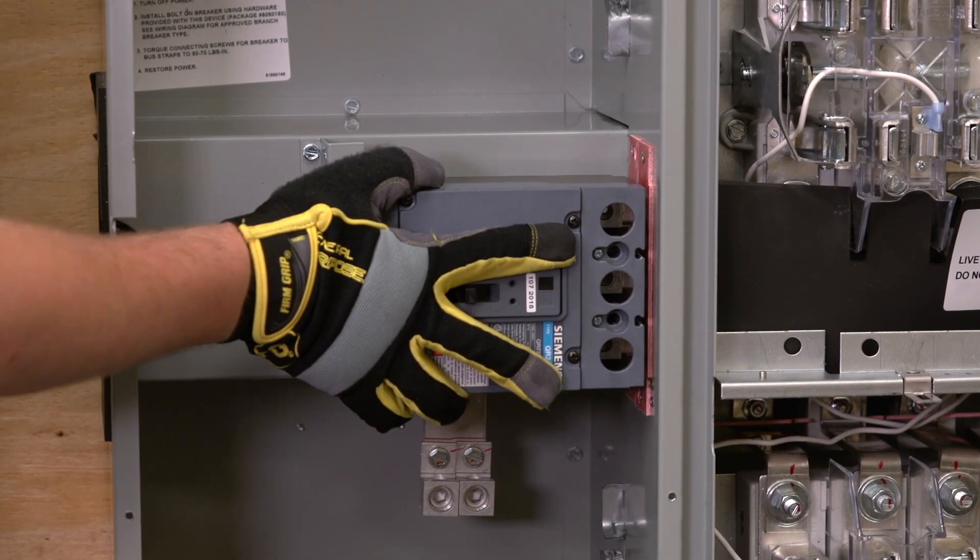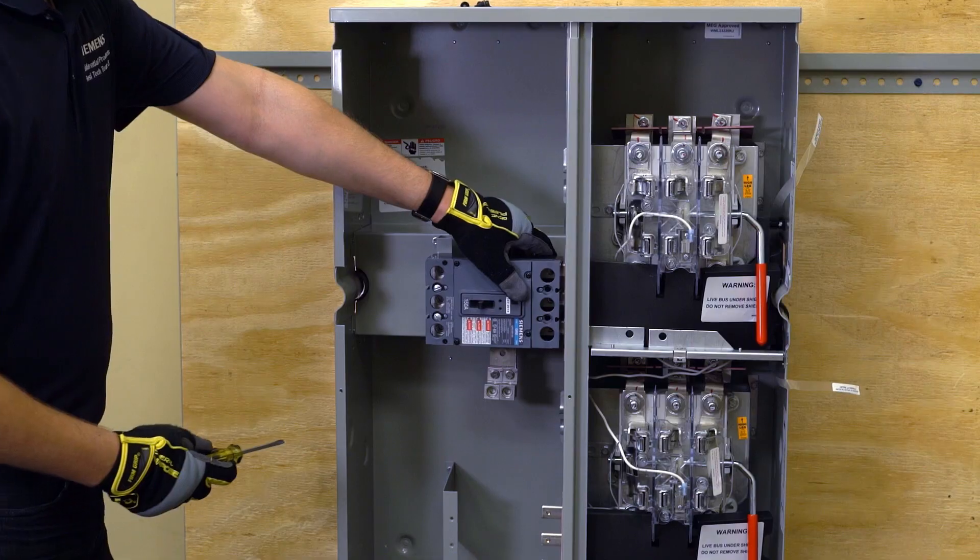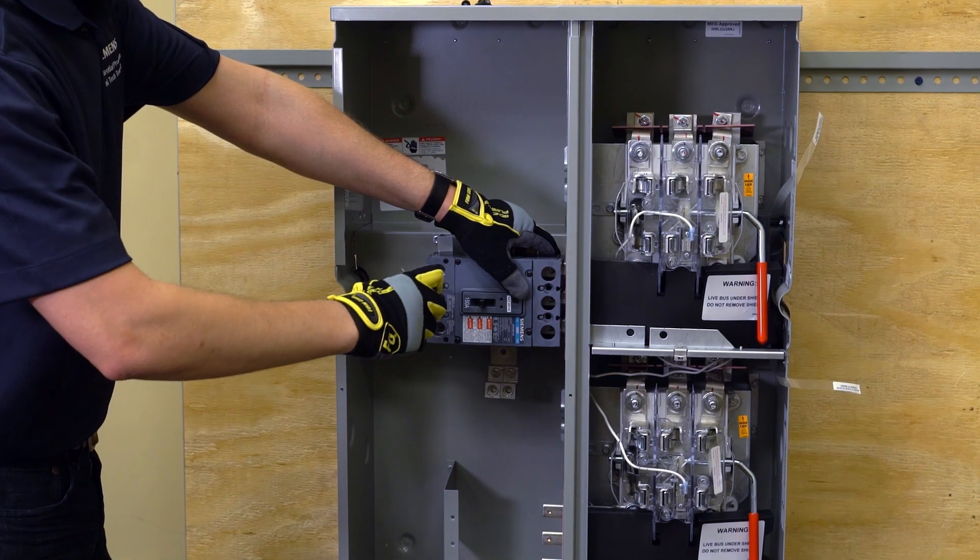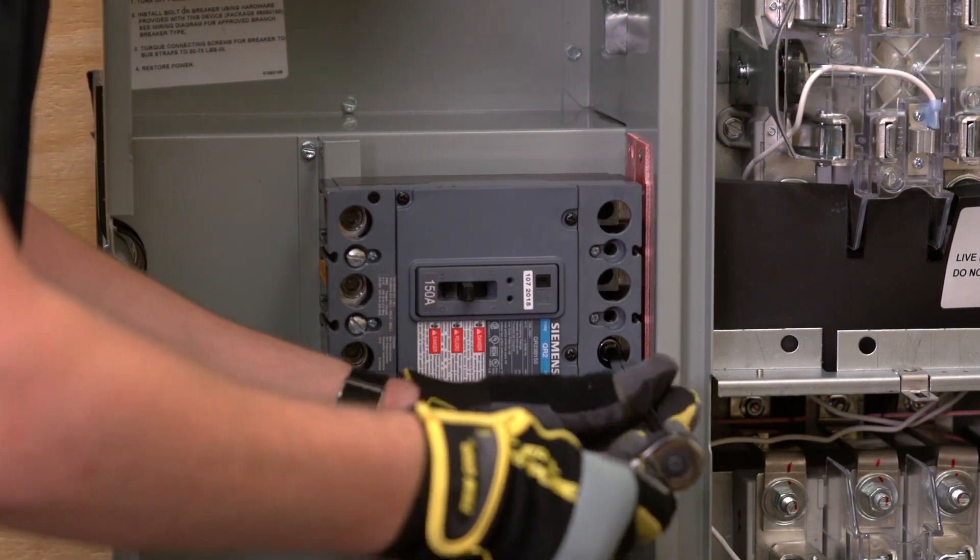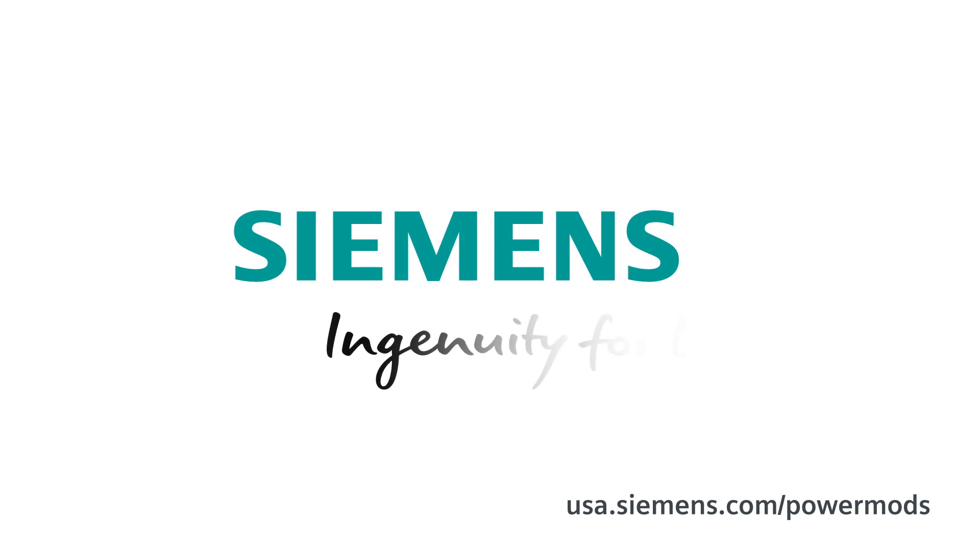To install the QR breaker, place it on the mounting base, fasten it down with the two longer screws, and then use the short black screws to fasten the phase straps to the breaker. Siemens. Ingenuity for life.